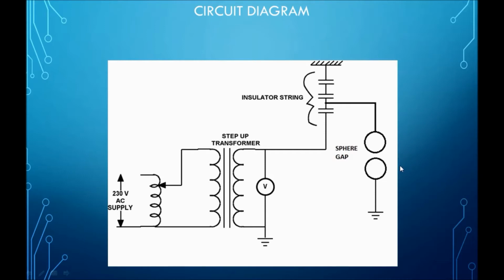Then what is the flashover voltage according to the IEC standard? 31.7. This is for the actual, not atmospheric condition. If the spark gap flashes over, then the voltage across these two insulators is 31.7 kV. This is the peak value. Then you can convert it to the RMS value.